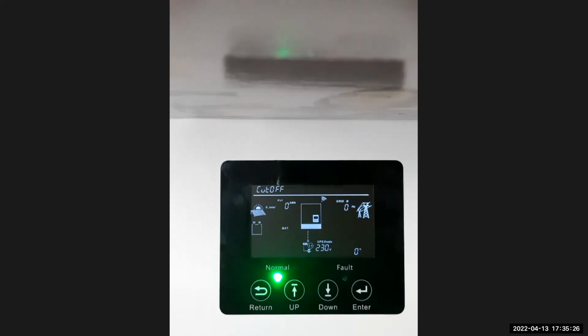Now number 11 is the setting where your inverter will completely shut down when it reaches this limit. On a lithium battery, it's an 80% DOD that you really want to use. It can go up to 90, but I don't like it at 90%. So it's a 20% setting. At this moment, this battery will be drained until 20%. When the battery reaches 20%, my inverter will cut off and stop using the batteries, and it will switch off until there's a sufficient amount of power from the panels to start charging the batteries, and it can go on again. So that's number 11 and 12. These two settings go hand in hand. You must work with the settings in order, first 12, then 11. Otherwise, you can't do your settings.